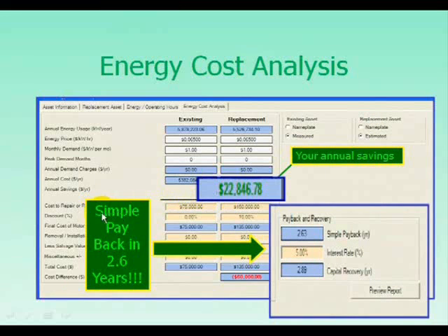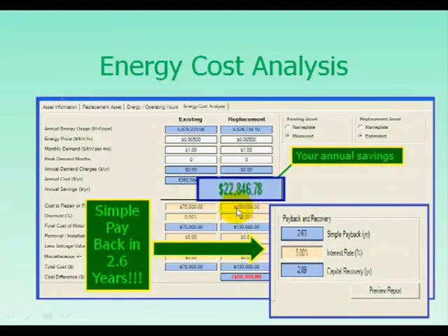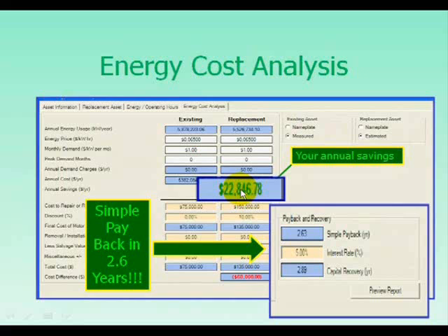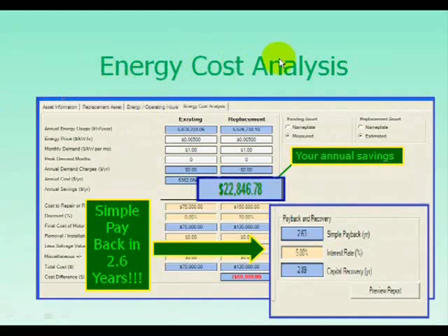This gives us a simple payback in 2.6 years and a capital recovery of 2.89 years. We have based our replacement cost at $150,000 to replace this asset versus a $75,000 repair cost. By subtracting the two and looking at our $22,846 savings, we can see that in 2.6 years we've paid for the replacement of this asset. Every year subsequent to that, you'll be saving this money towards the bottom line. In today's highly competitive world, it's important that we're looking at every avenue possible to reduce our costs.